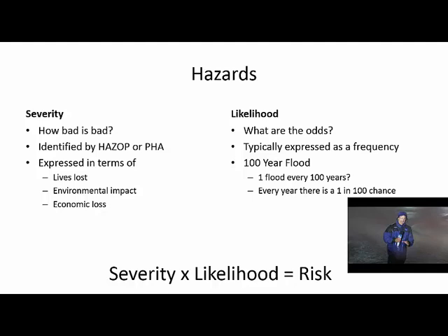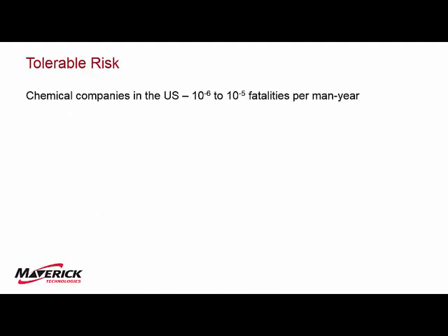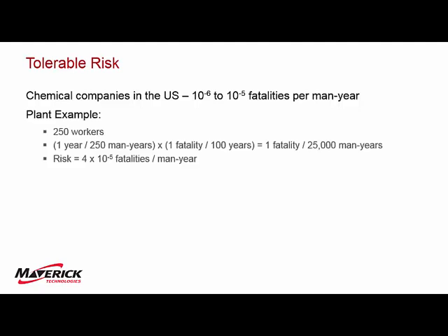It'd be great if we could design all the facilities so there was zero risk of injury. But as an engineer, you know that's not possible. So how small does the average frequency of a fatality need to be for a plant to be considered safe? The chemical companies in the United States typically operate in the 10 to the negative 5 to 10 to the negative 6 fatalities per man year range. This describes the risk to a single employee in a year. So those are some little numbers, and I don't know if they mean anything to you, so let's go through an example.